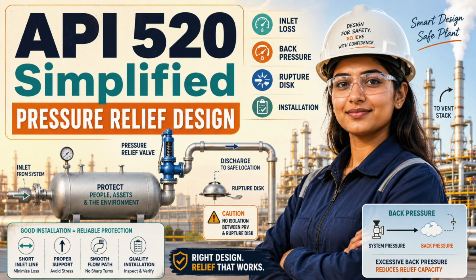Now consider oversizing. Many engineers still believe that a larger relief valve is automatically safer. It is not. If the required relieving flow is far below the capacity of an oversized valve, the valve may open, rapidly depressurize the local inlet volume, close, experience pressure recovery, and reopen. That cycle can become chatter. Chatter can damage the seat, disc, spring, guide, bellows, piping, and nozzle. It can also reduce effective relieving capacity.